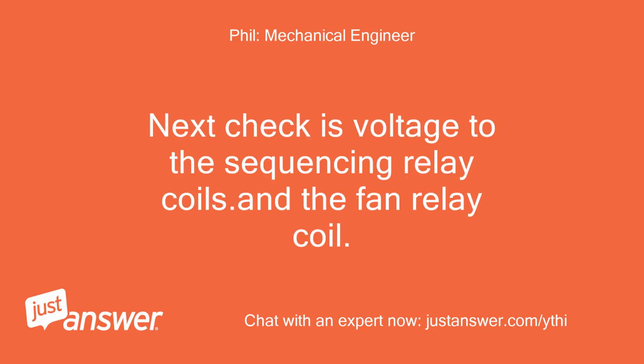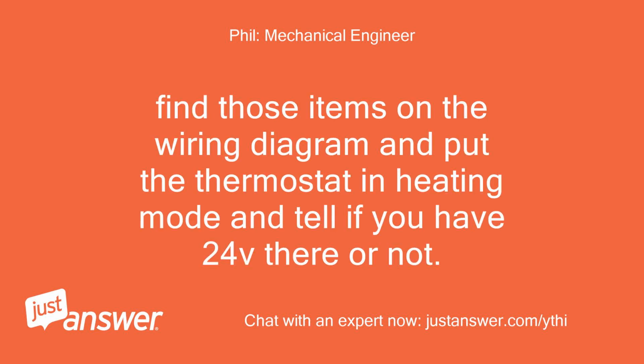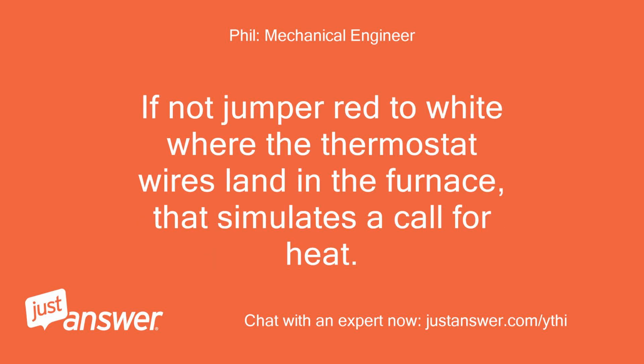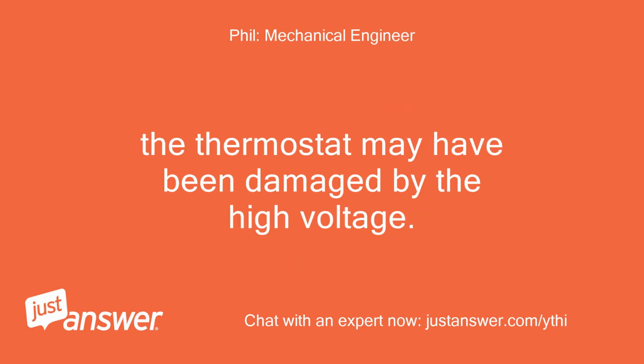Next, check the voltage to the sequencing relay coils and the fan relay coil. Find those items on the wiring diagram, put the thermostat in heating mode, and tell me if you have 24V there or not. If not, jump a red to white where the thermostat wires land in the furnace. That simulates a call for heat. The thermostat may have been damaged by the high voltage.